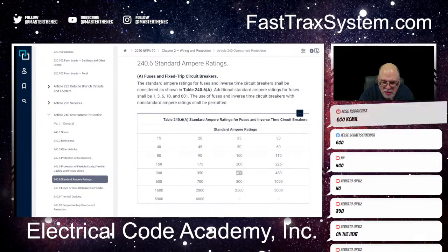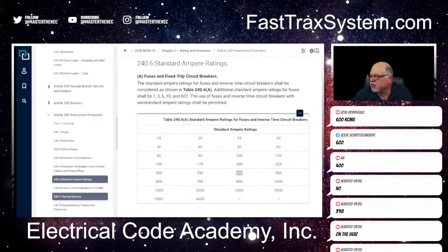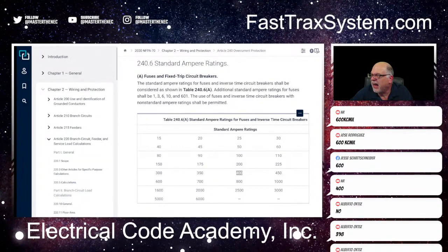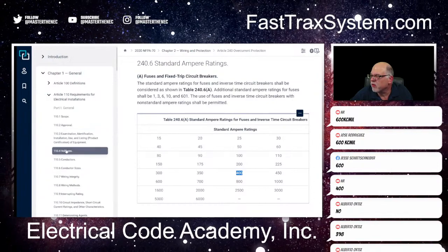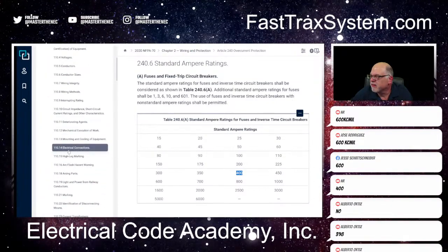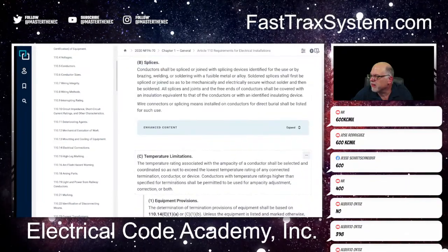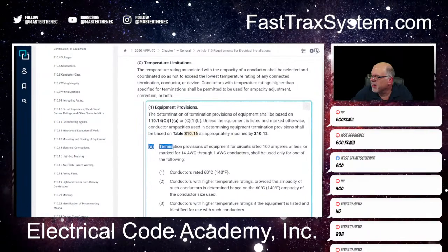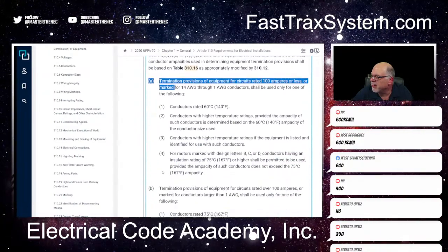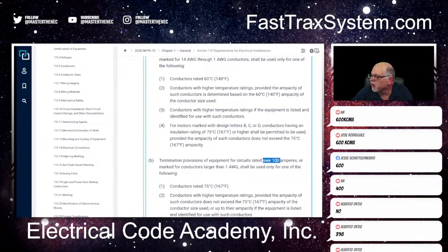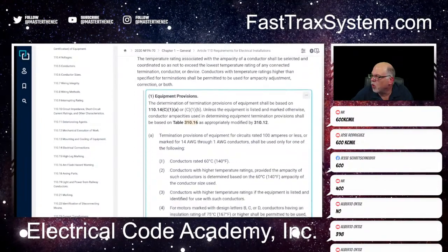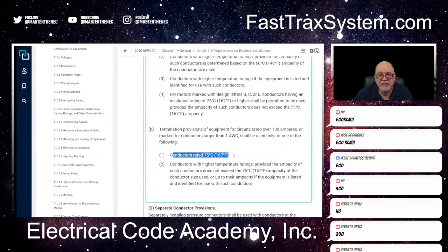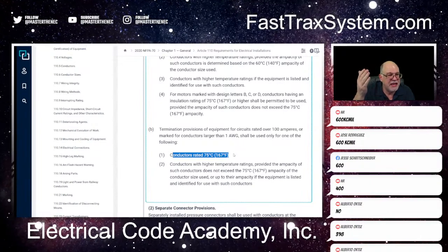I get those so screwed up here. So let's go to the NEC while we're here in this journey. Let's look and see another reason why we're going to be at 75, because I get this question an awful lot. So here's 14, here's C. So C1A, okay? But in our case, it is over 100 amps, so we're doing C1B.